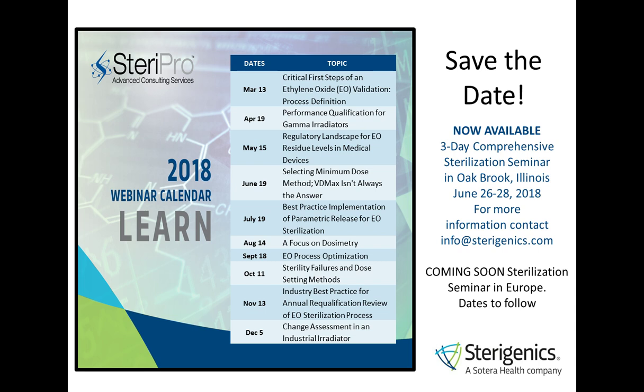Now, if you have a change in your product line, or a change in your sterilization process parameters or your load configuration, then it's always a good idea to reevaluate that external PCD to make sure that it's still comparable to possibly that new product that you're bringing in or that new parameter change that you have. Because changing parameters could adjust that relationship between the internal PCD and the external PCD.